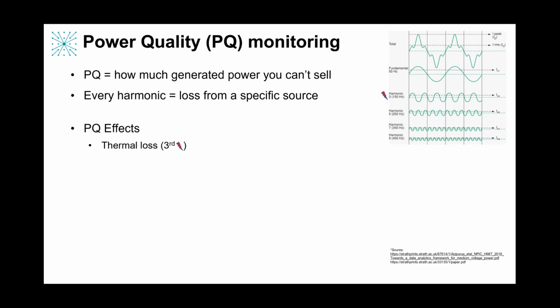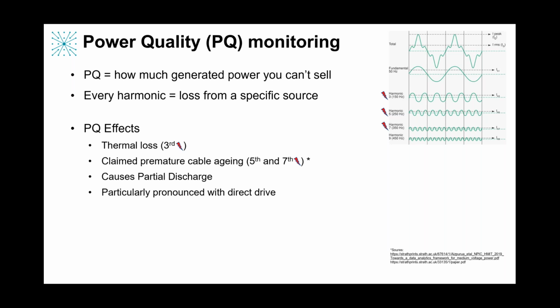So the third harmonic here, for example, is typically associated with thermal loss, like an overheating transformer, which we often instrument in digital power stations, but it could also be that overheating cable again. It's claimed in the academic literature that the 5th and 7th harmonic, if they're very prevalent in a place, that's probably a critical cause of premature cable aging, which in itself all leads to partial discharge and overheating, and it's a particularly pronounced problem with direct drive turbines. So power quality really matters because it's a fundamental source of the problem.